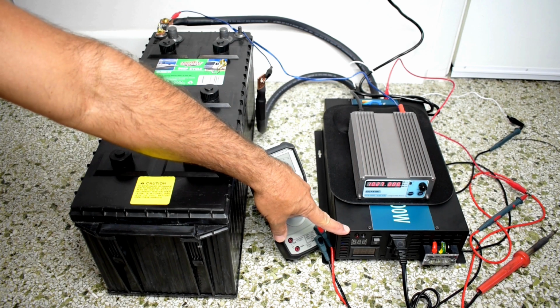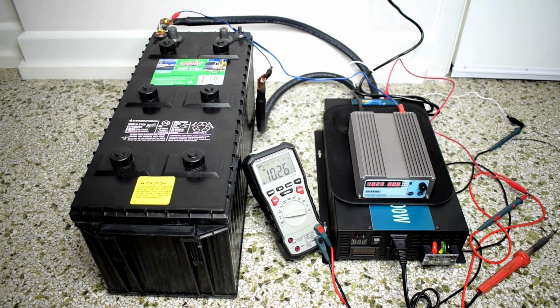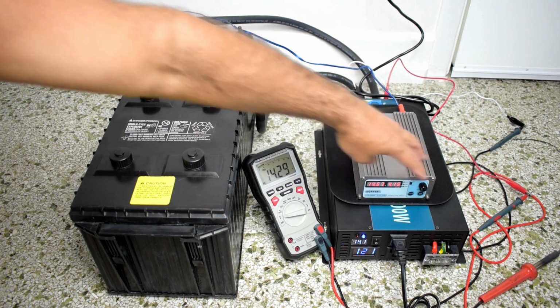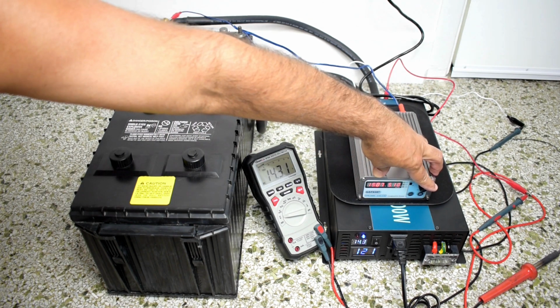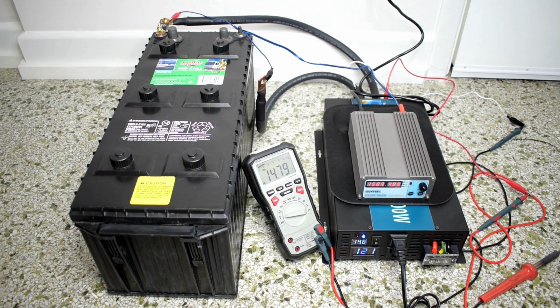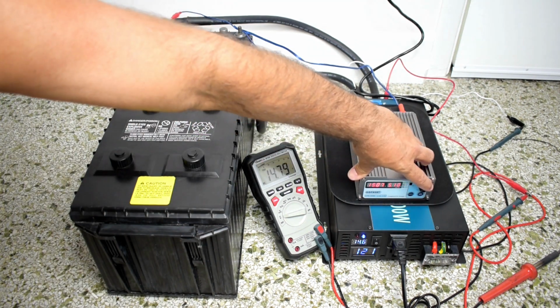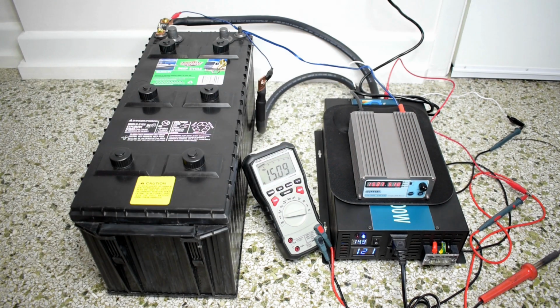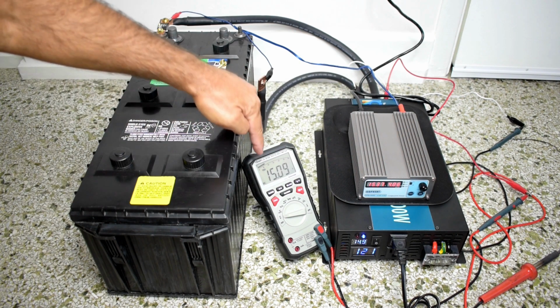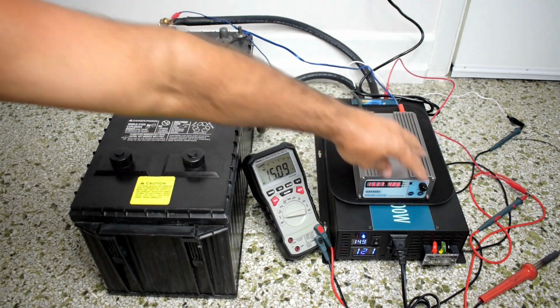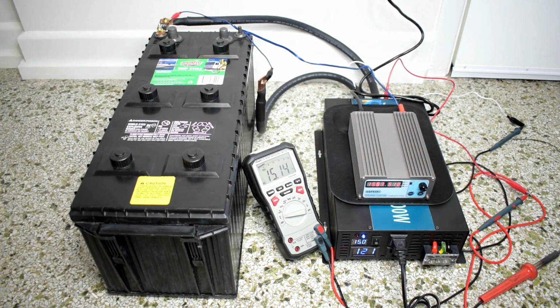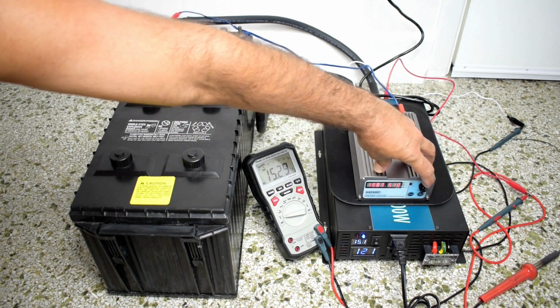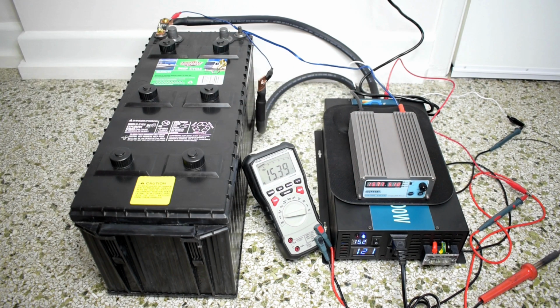We're going to increase voltage higher and higher to make sure it turns off. 14.1. We're at 15. Voltage is staying about the same level. Let's go. We're at 14.9, 15 volts. Let's go a little higher. 15.1. The alarm should sound very shortly if it's going to be working properly.